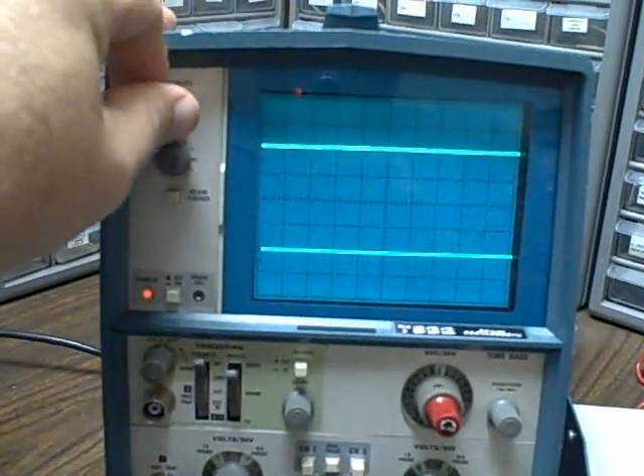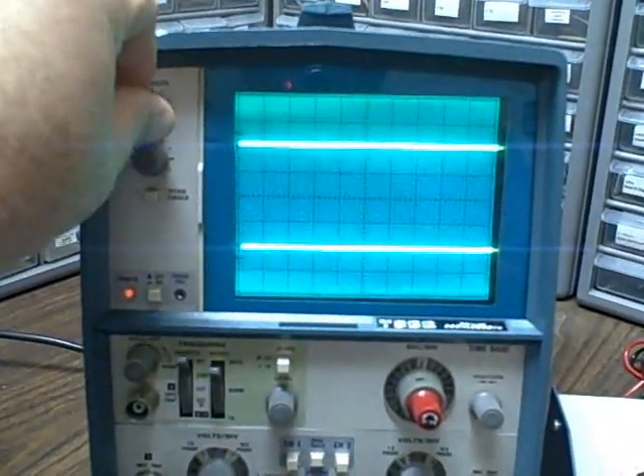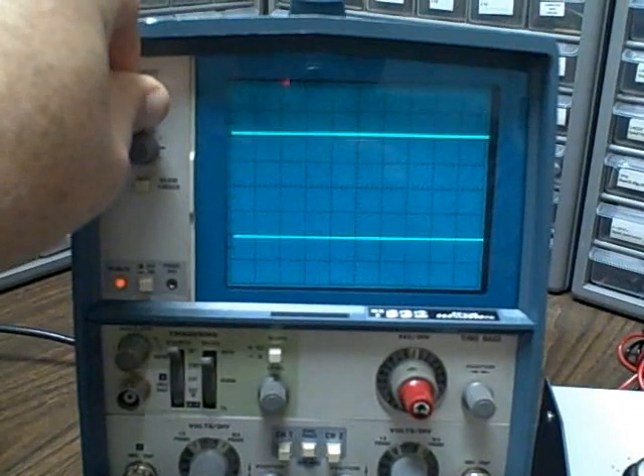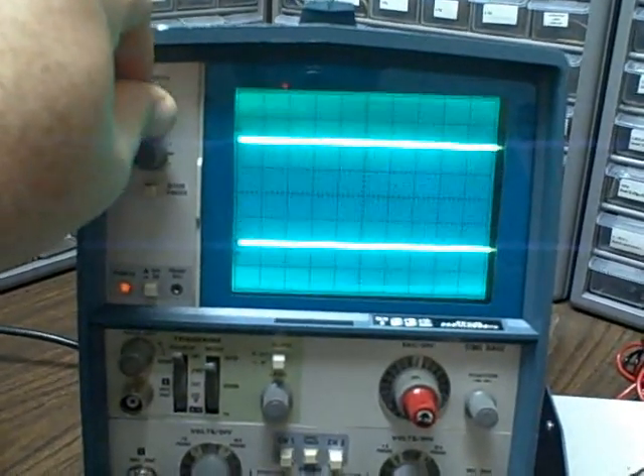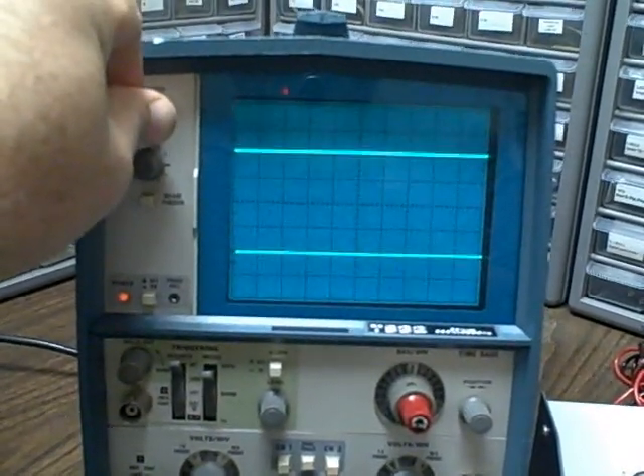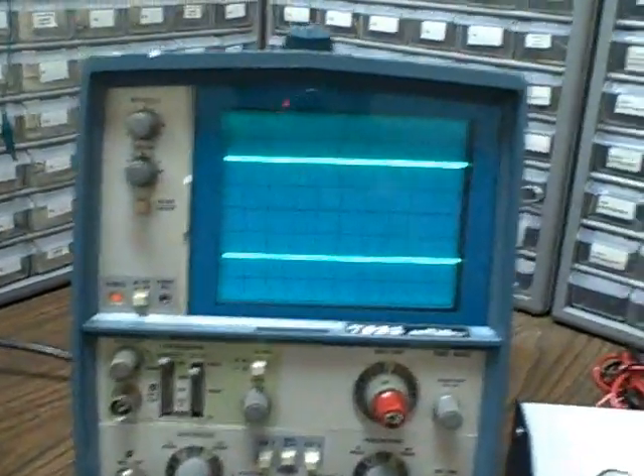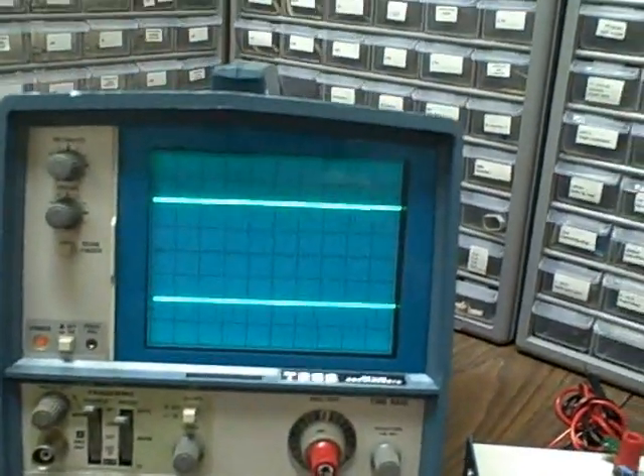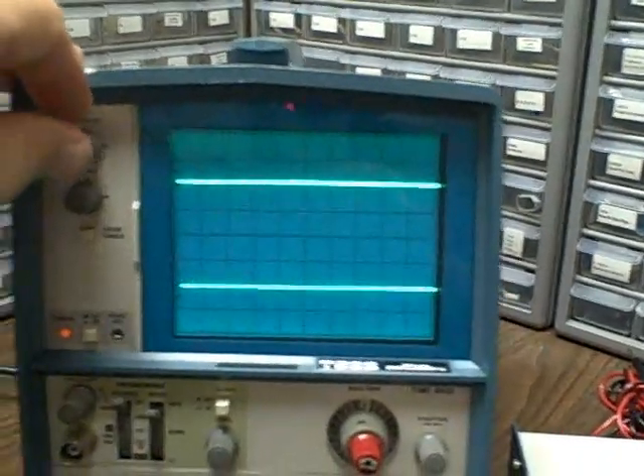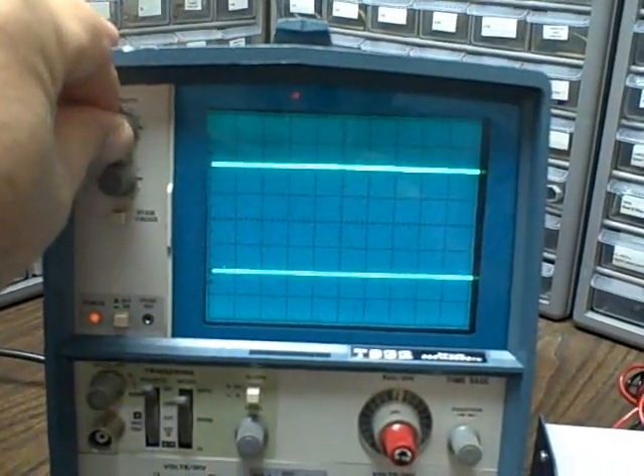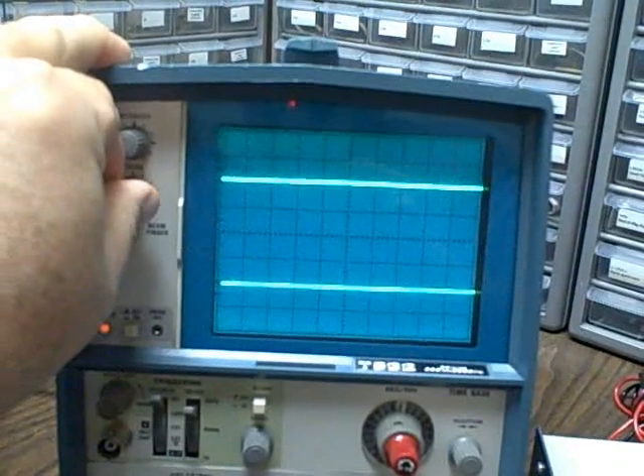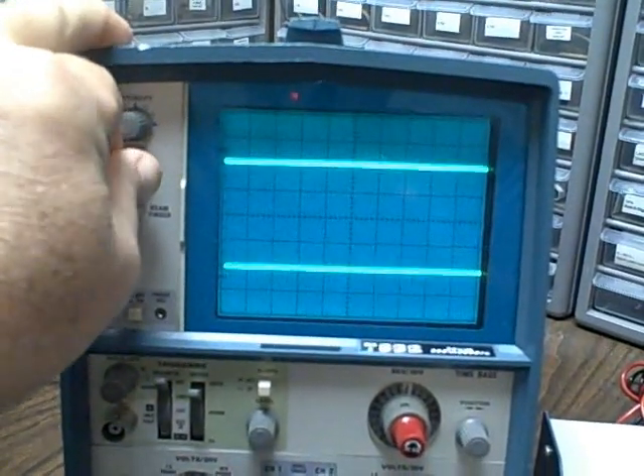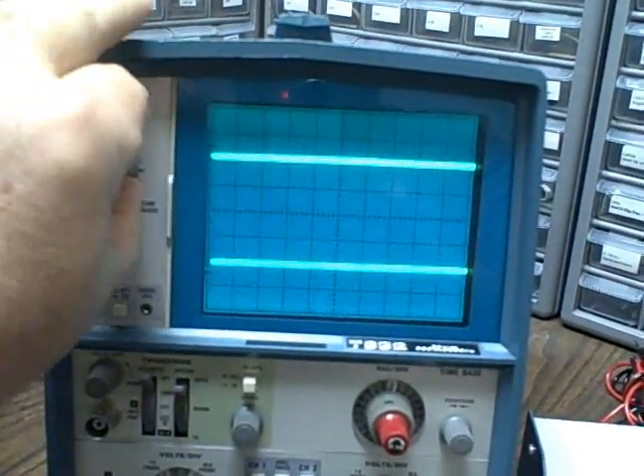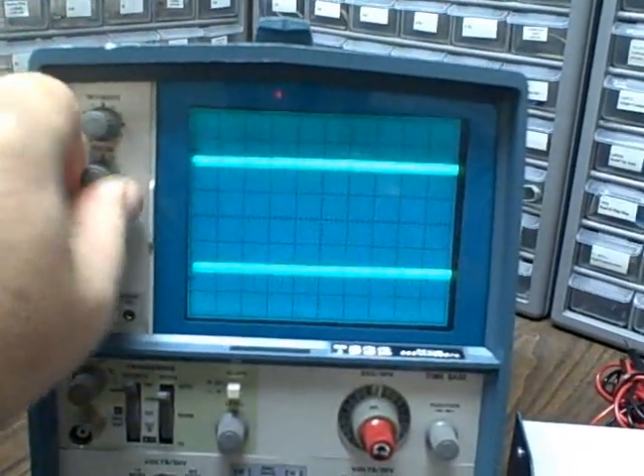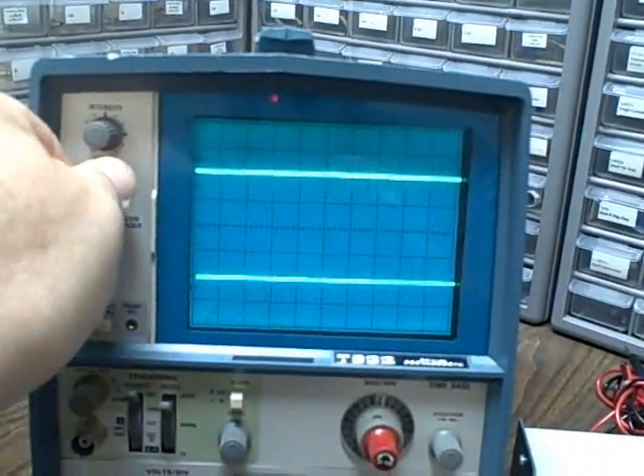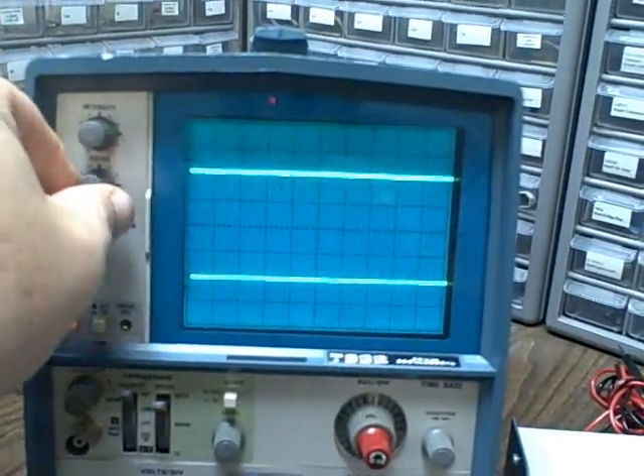All right, we have the intensity control for the beam. We have plenty of intensity here, much more than we need, but that's good, because as your frequency goes up, you may need to increase it, or as the years go by, it's possible that the tube could lose some strength and you need to intensify the beam. We have a focus control with which we sharpen the image.